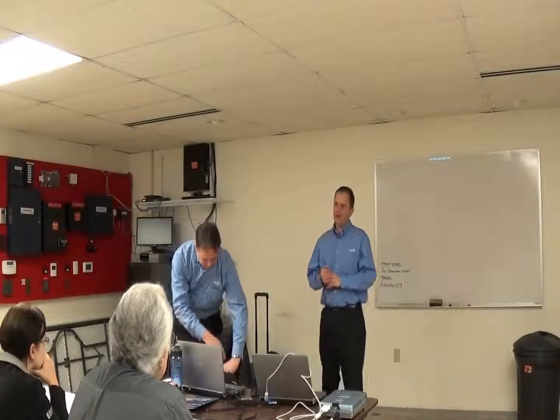So, we talked about this in a plan and spec job. I did it for a long time, guys. I did a lot of estimates, and I would count VAV boxes. I knew what the cost per VAV box was. That's how I estimated the job. I didn't really always look at the specs, and I kinda knew what I was gonna put in. Same way with the mechanical guy. He's gonna look at it and say, I got 82 VAV boxes, I know a triple duty valve costs X for this, so it's $400 a box, boom, I'm done. Well, now we didn't get that savings, because he's still working off of pressure dependent.